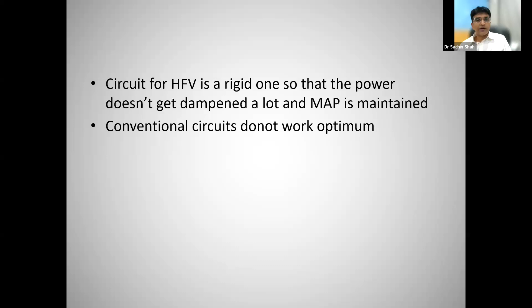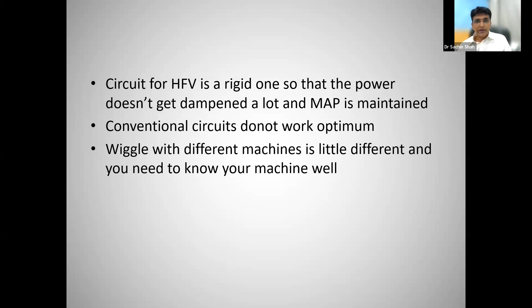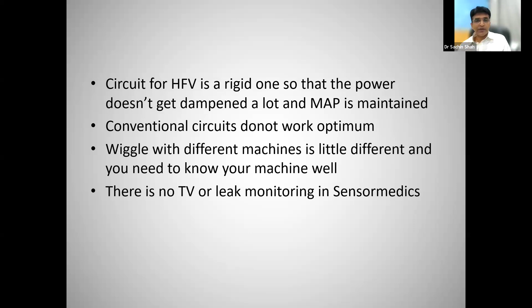Even for other ventilators like the Fabian and the SLE, they have a rigid circuit for the high frequency. The wiggle with different machines is different, and you have to know your machine very clearly. The wiggles on the Sensormedics are different as compared to the wiggles on the Fabian. So you have to understand and know your machine very well. There is no tidal volume monitoring in the Sensormedics, so it is a black box. There is nothing that you can monitor. What you can monitor is only clinically the vibrations, and you can do blood gases to see the carbon dioxide levels and the PO2.